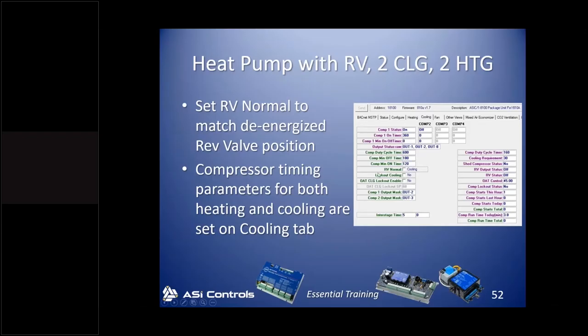For heat pump personalities, a script running in the background will show the setting called RV Normal. That can be unchecked in cooling or checked in heating. RV Normal says: when the reversing valve output is off, what do I get when the compressors run? RV Normal Cooling means turn on the reversing valve output when you need heat; RV Normal Heating means turn on the reversing valve output when you need cooling.